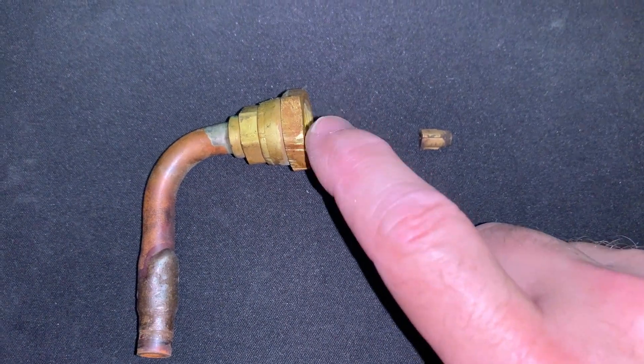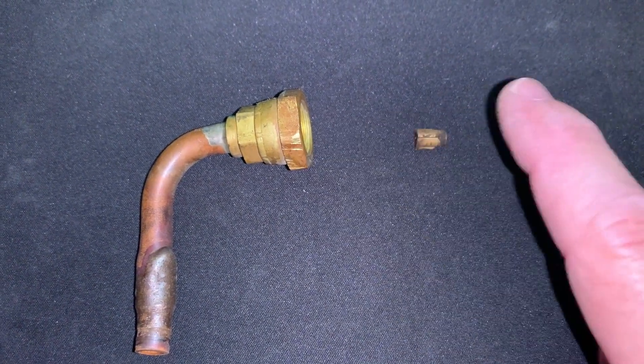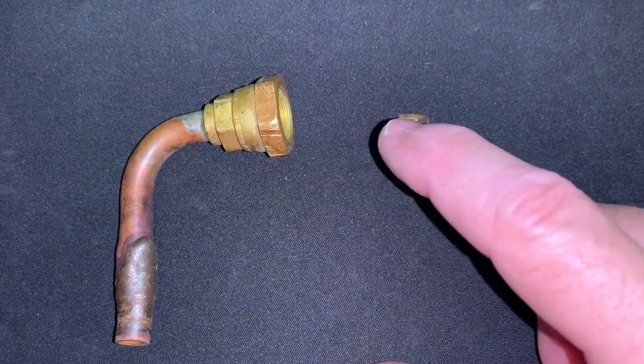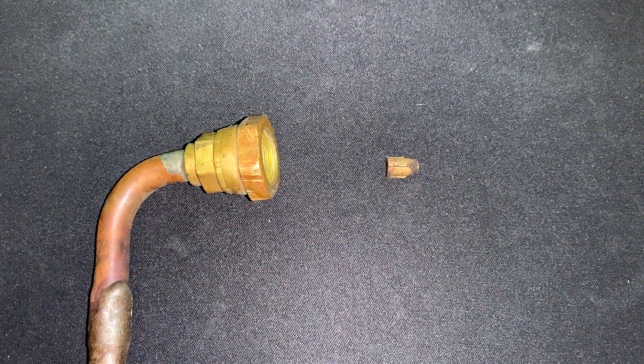There's a little gasket that kind of sits in the connection over here that this piston pushes up against, and then your liquid flows in here through the orifice. You get the low pressure side of the orifice that gives you your cooling effect in the evaporator coil.